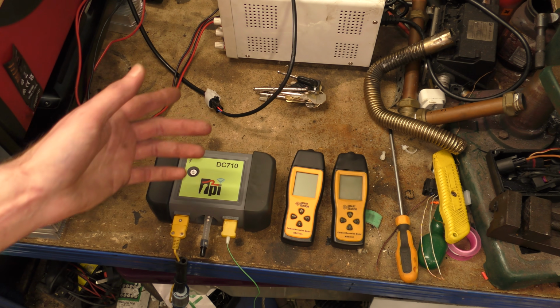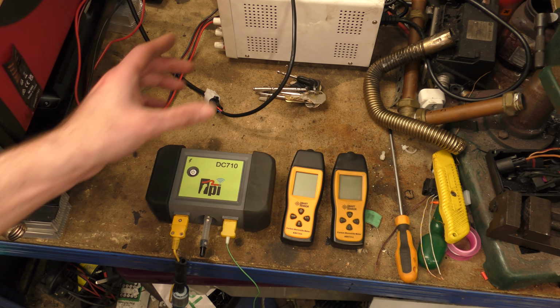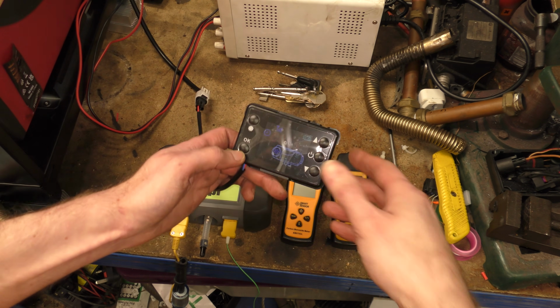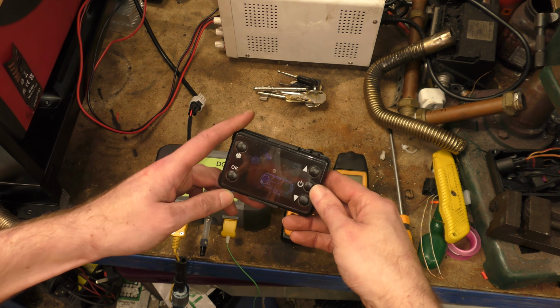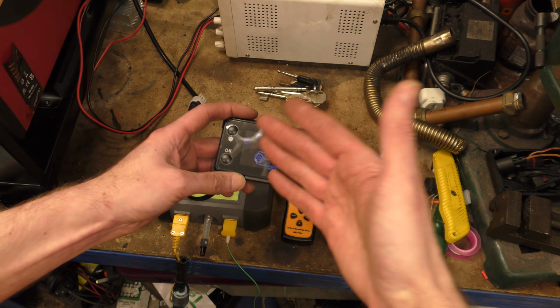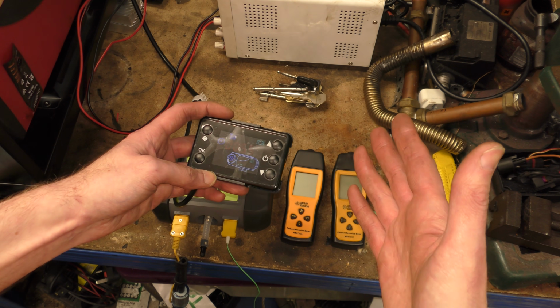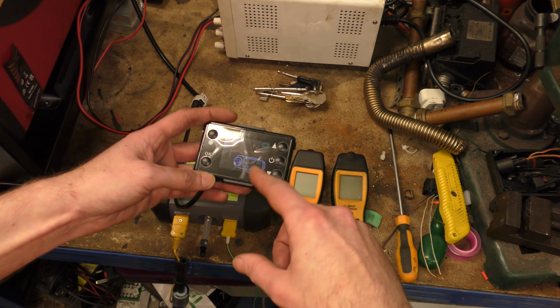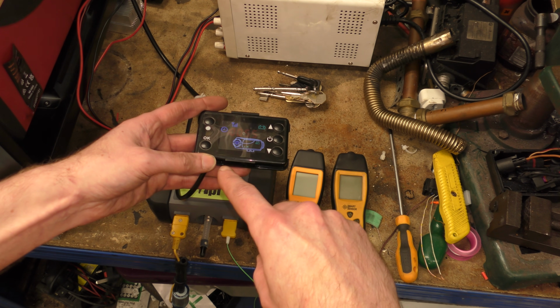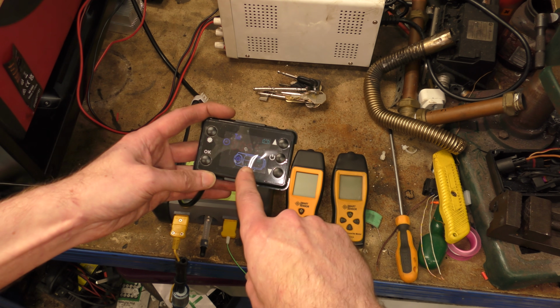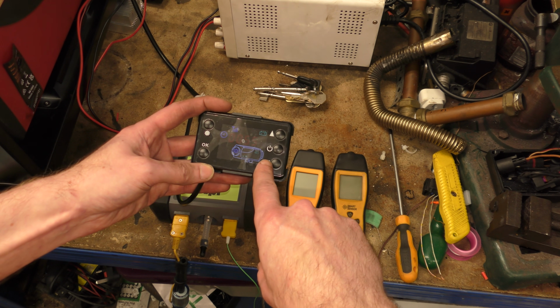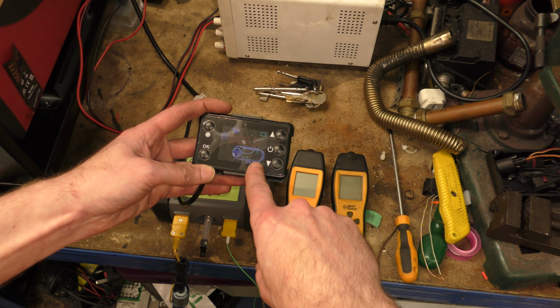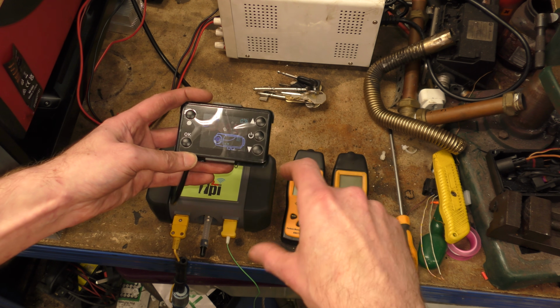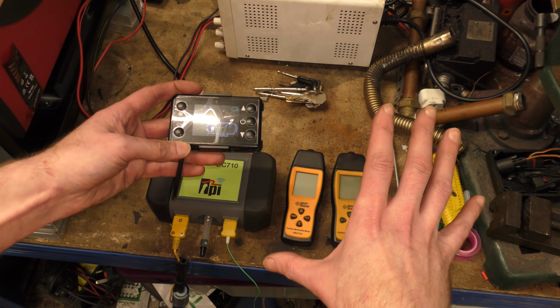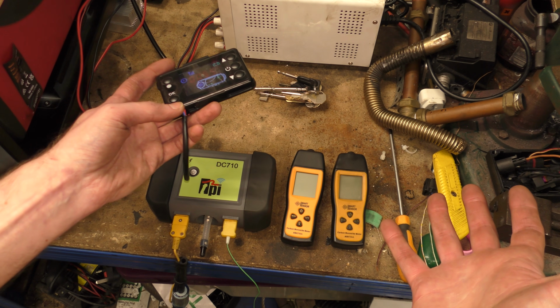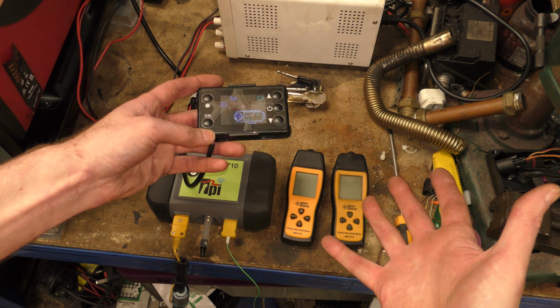A few people have sent me the video of the guy tuning them with no tools whatsoever. I don't want to ruin what he said by paraphrasing it, but you're basically adjusting the fuel and air and waiting to get 2 red bars, then waiting for 1 red bar to go out, then turning it up a little, and that's it tuned as good as it's going to be. I don't know if this is accurate, and it's something I'd like to test using our combustion gas analyzer and carbon monoxide meters.